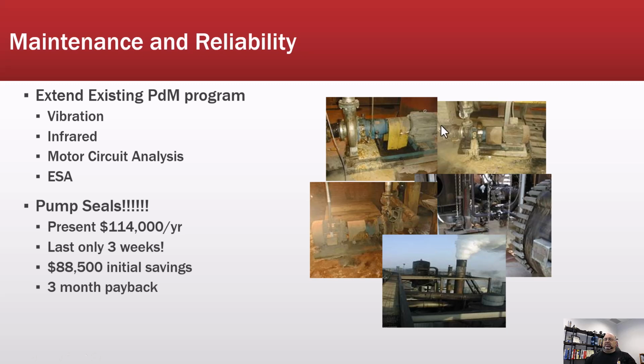improvements. The pump seal issue, because we saw pump leaks everywhere, and all of this stuff ends up getting washed down and going through waste treatment, and that's MASH, that's actual product. Presently, at the time, I should say, they were paying about $114,000 per year in pump seals. Somebody had come along and thought that they would save money by going from a double seal that these were all originally designed for and switching over to a single seal, which were only lasting about 3 weeks before they'd start leaking again. And then they'd have to go through there, which didn't just waste time of everything. That's a wasted time of the maintenance staff who were then no longer doing their planned maintenance. But we saw that as a simple 3-month payback by going back to the original seal types that weren't leaking very often.